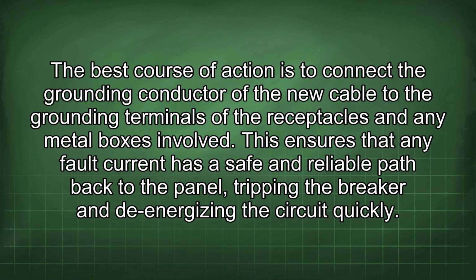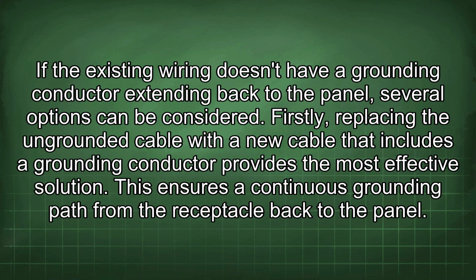The best course of action is to connect the grounding conductor of the new cable to the grounding terminals of the receptacles and any metal boxes involved. This ensures that any fault current has a safe and reliable path back to the panel, tripping the breaker and de-energizing the circuit quickly. If the existing wiring doesn't have a grounding conductor extending back to the panel, several options can be considered.